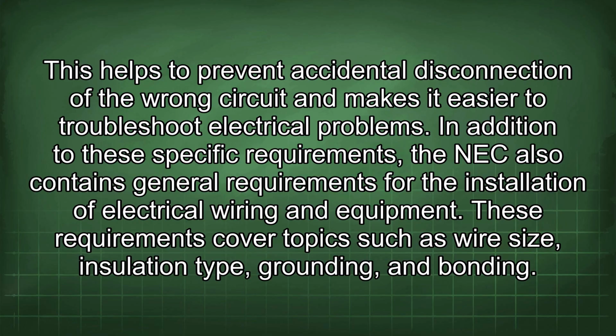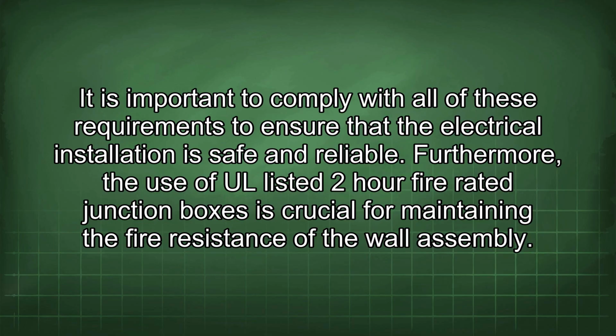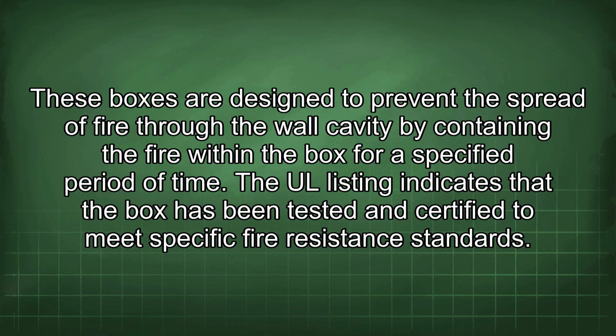In addition to these specific requirements, the NEC also contains general requirements for the installation of electrical wiring and equipment. These requirements cover topics such as wire size, insulation type, grounding, and bonding. It is important to comply with all of these requirements to ensure that the electrical installation is safe and reliable. Furthermore, the use of UL-listed 2-hour fire-rated junction boxes is crucial for maintaining the fire resistance of the wall assembly. These boxes are designed to prevent the spread of fire through the wall cavity by containing the fire within the box for a specified period of time.